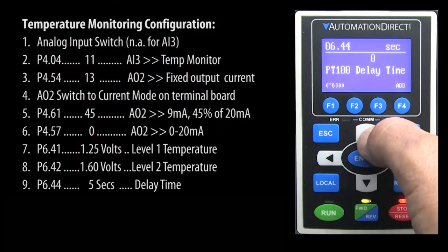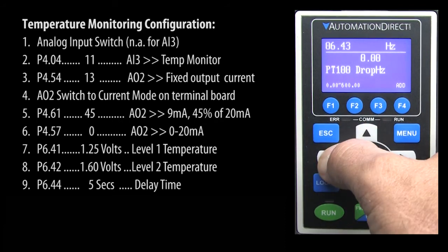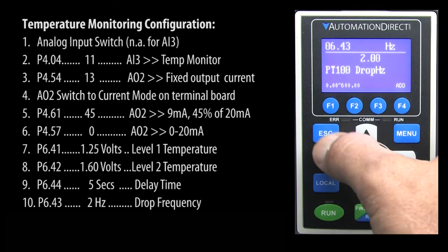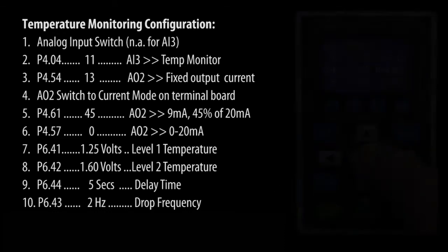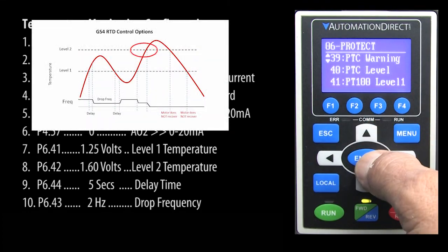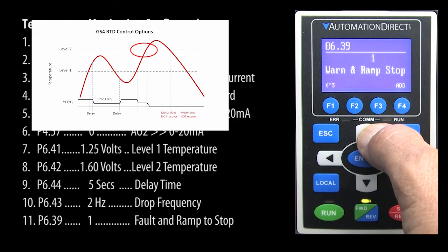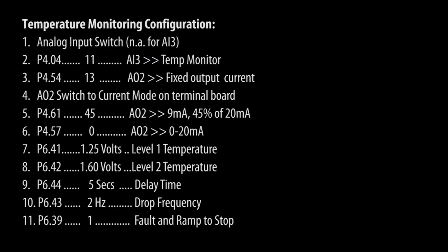Just be sure level 1 parameter is non-zero and below level 2. So, when we hit level 1, let's delay 5 seconds and if we are still at level 1 after the 5 seconds, drop the drive's frequency to 2 Hz. Remember this number has to be greater than 0 if you are using an RTD. Putting a 0 in here turns off the RTD function and enables the PTC function. If we hit level 2, then immediately do whatever is in parameter 639. In our example, we'll fault and ramp to a stop. That was a lot of parameters, so here's a summary of what we just did.